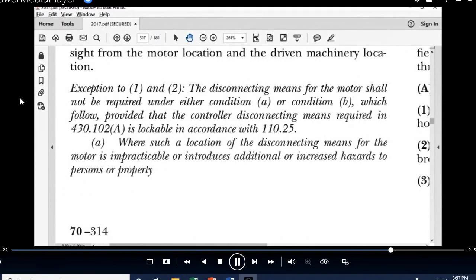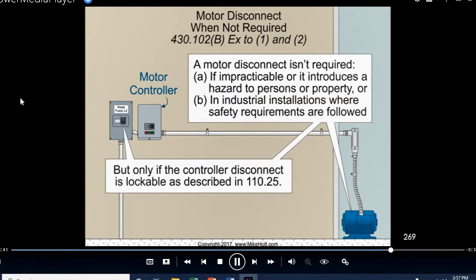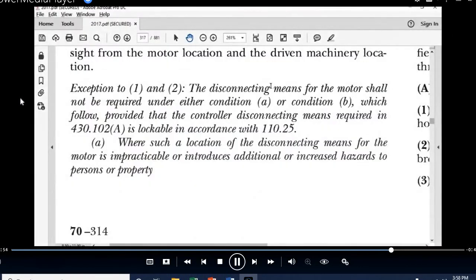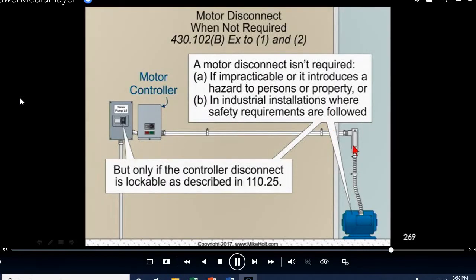Now this is the motor disconnect. The disconnecting means for the motor shall not be required under condition A or B, which follow, provided that the controller disconnecting means is lockable in the open position in accordance with 110.25. So go over here. This disconnect for the controller has to be within sight of the controller. There's never an exception there. But you have to be able to lock the disconnect for the controller before you can use the exception. Here's what the exception says. You don't have to have a disconnect within sight of the motor.